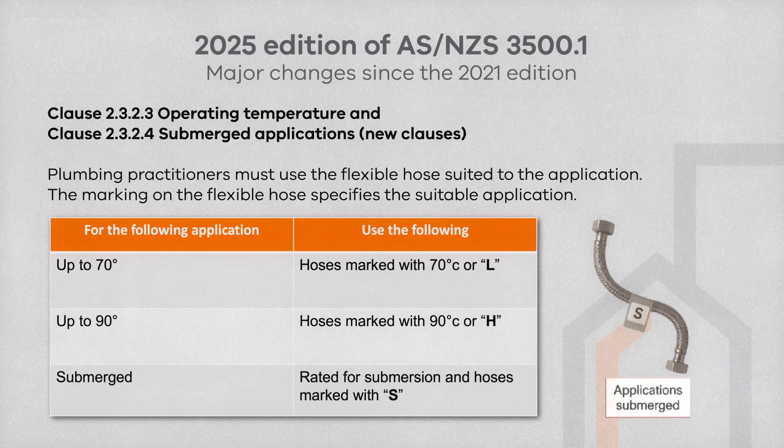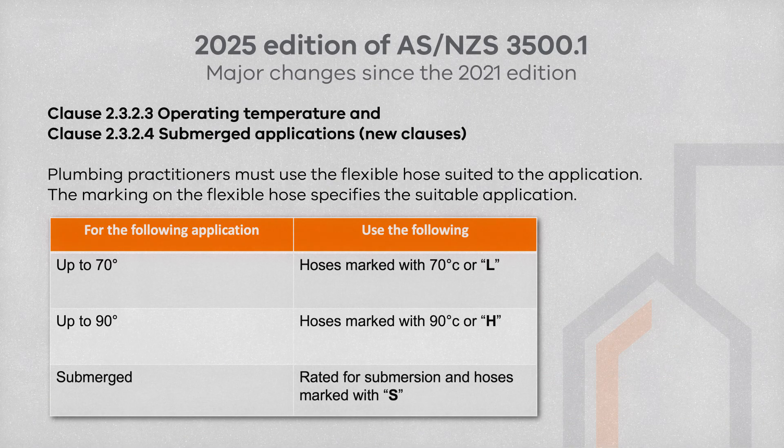A situation where you would use a flexible hose marked with an S would be in the top entry cistern for a water closet, as it's going to be sitting in water. It is important to ensure the correct hoses are used, as they are relevant in systems where pressure ratings are critical for safety and performance. Always refer to manufacturer's specifications for further information on the limitations of the hose application.